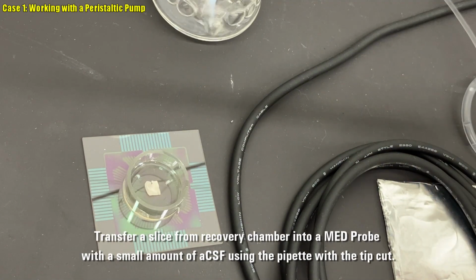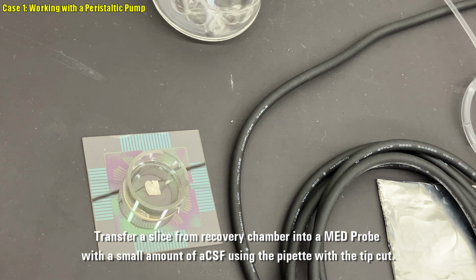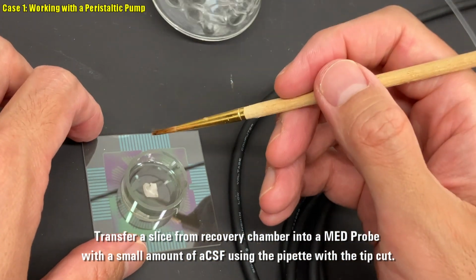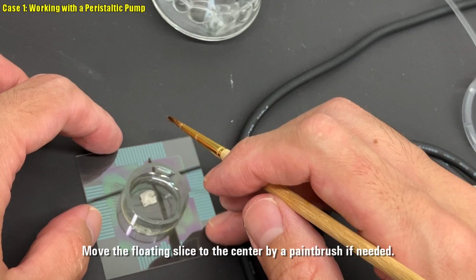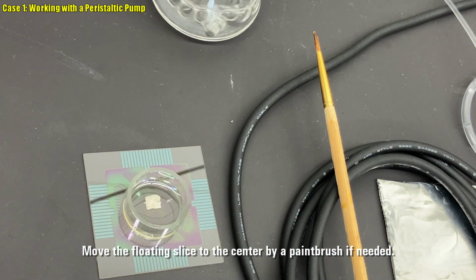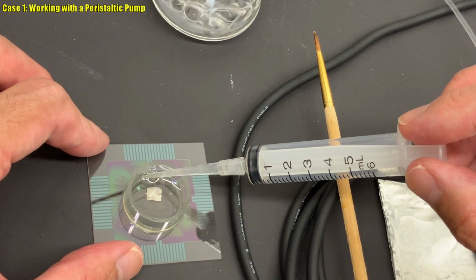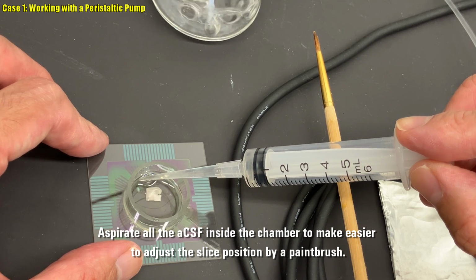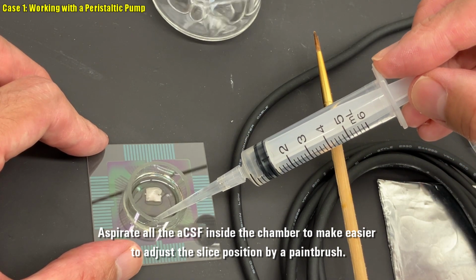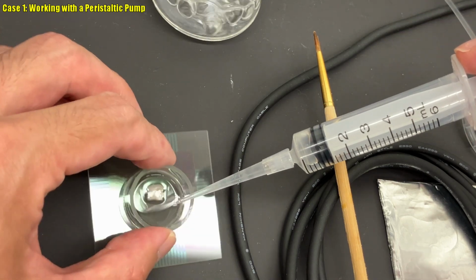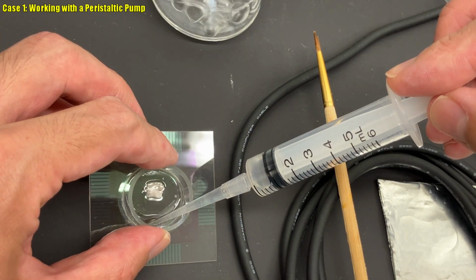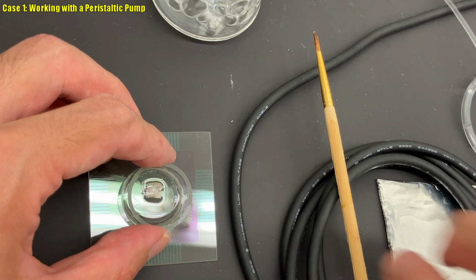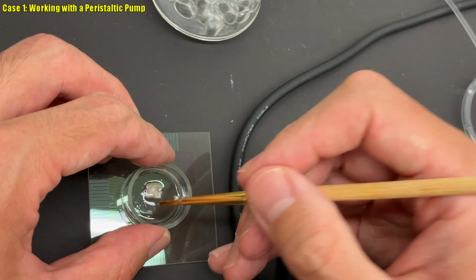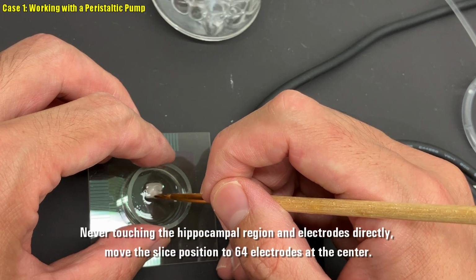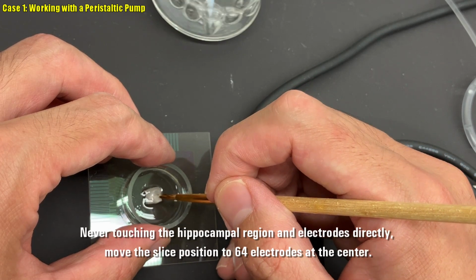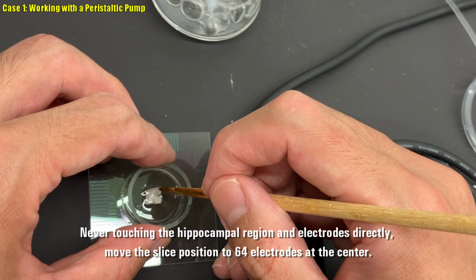Transfer a slice from recovery chamber into a MED probe with a small amount of ACSF using the pipette with the tip cut. Move the floating slice to the center by a paintbrush if needed. Aspirate all the ACSF inside the chamber to make easier to adjust the slice position by a paintbrush. Never touching the hippocampal region and electrodes directly, move the slice position to 64 electrodes at the center.